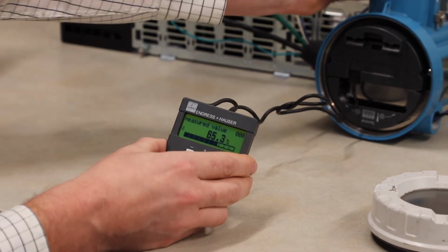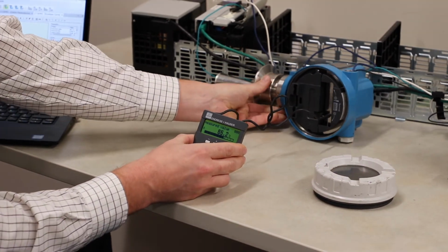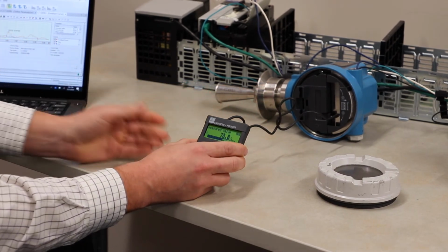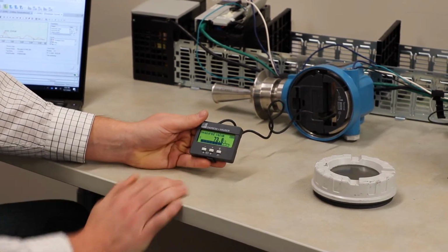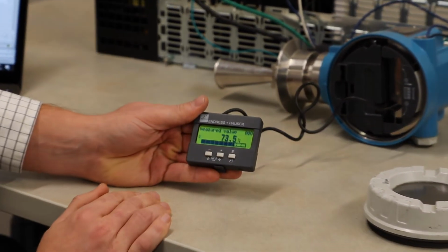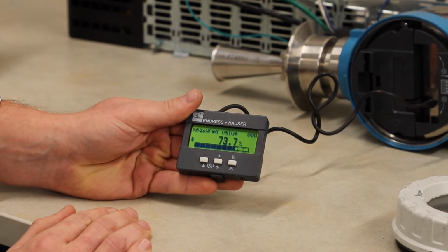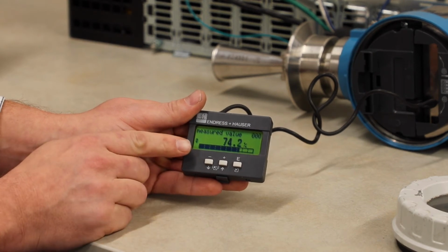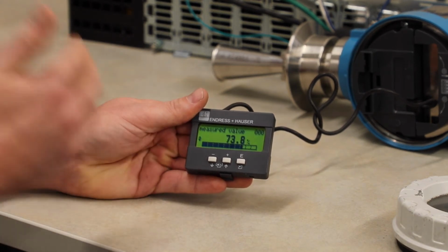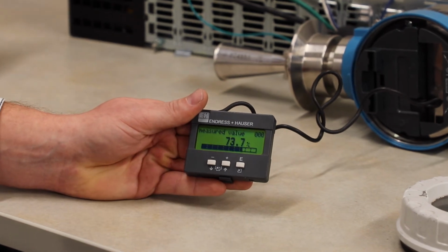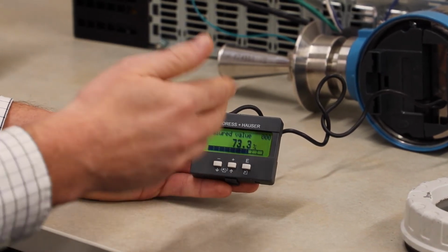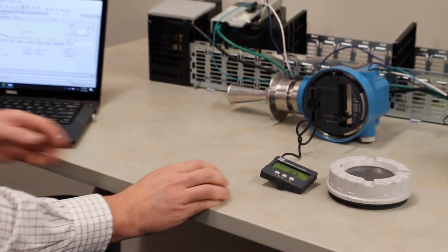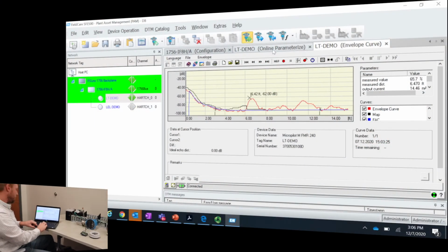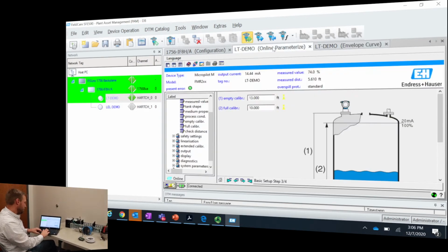We're going to turn this to aim at a different target. Right now it's aiming at the door behind me. We'll give it a little bit of time here to even out. And there it is. So you can see the actual level changed. It's now reading an echo from something closer to it than the ceiling is. The door is closer than the ceiling is, so our measured value increased. And you can also see that update here on the computer as well, on our connection as well, 74%, which is roughly what the display shows.